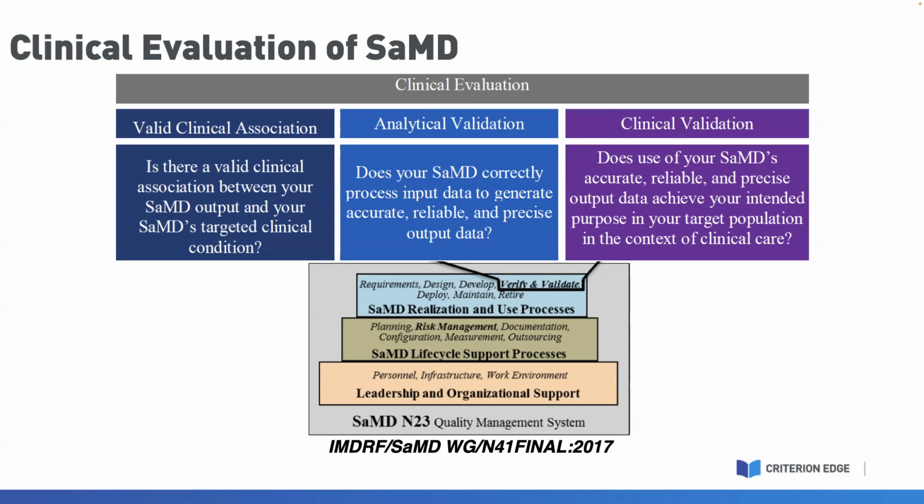For the purposes of the IMDRF guidance, that valid clinical association, that's your scientific validity. That's used to refer to the extent to which the software's output is clinically accepted or well-founded. So you want to look at the full body of evidence, and you want to reassure the notified body that in order to establish that scientific validity, the software's output corresponds accurately in the real world to the healthcare situation and to the condition which you've identified in your software definition statement. A valid clinical association is really going to be critical before you even get started.